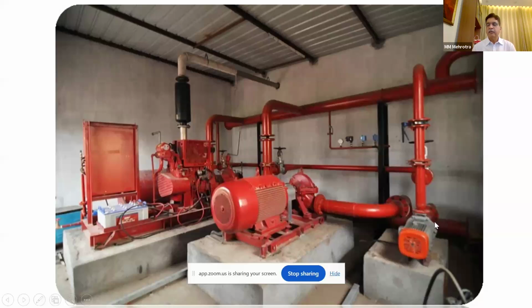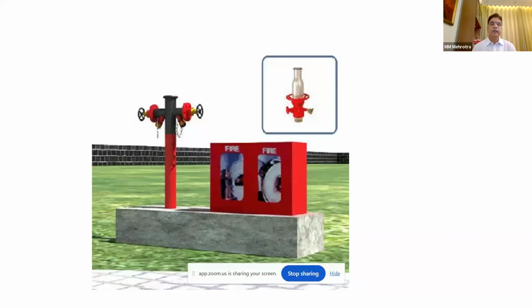What is the work of this jockey pump? The jockey pump will have a pressure sensing device. The moment the pressure is below 5, it will operate and maintain the pressure. Pressure may fall because of certain minor leakages and other things. So it will ensure that if there is a fire and anybody wants to fight the fire, then water is available at full pressure. So this water is coming to these water points for fighting fire.